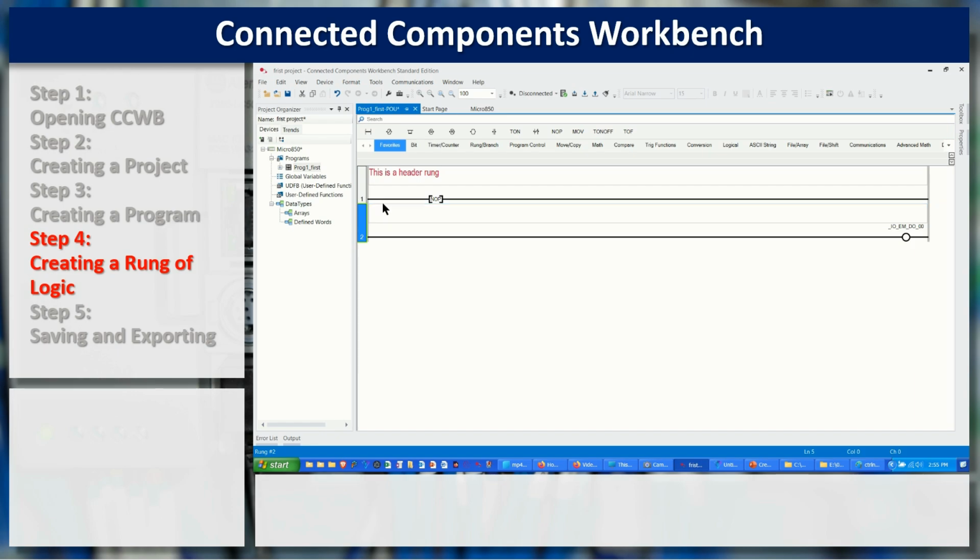The second part is, this is actually a working rung. Now it only has one application. This rung is called an unconditional rung. There's nothing preventing it from starting, and also nothing to stop it. The only way we can stop it is to turn the PLC from run mode to program mode. That'll turn it off. Or we kill the power to the PLC, or if it's on another panel with the disconnecting means, we kill the disconnect. We're not controlling it. To do that, we have to put a contact ahead of it.